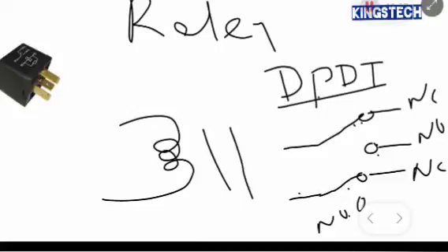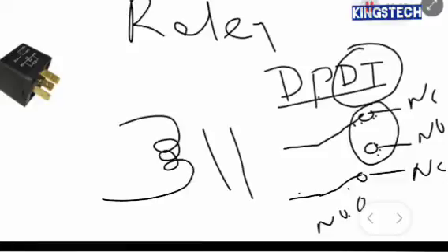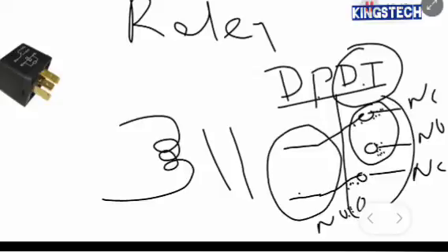So it has two output contacts here. The double throw. See the two output contacts. These two here, NC and NO. Just the same thing here. Double. So it has double of this contact, and it also has double of this contact. So that is what makes it a double pole, double throw relay.